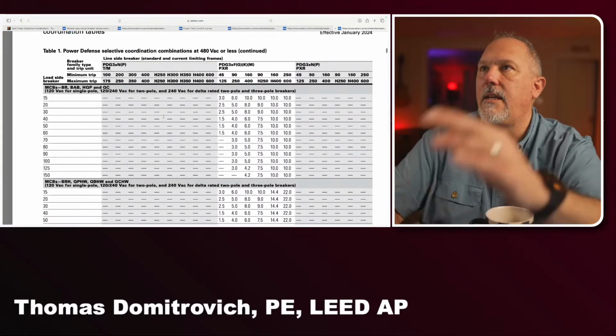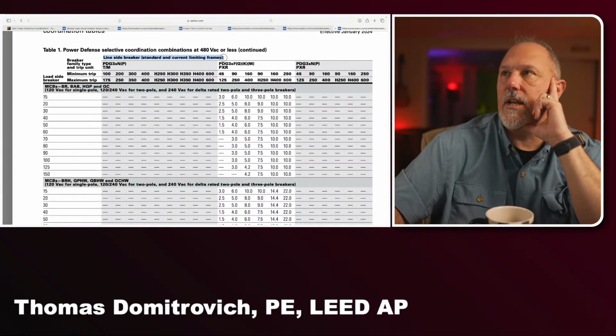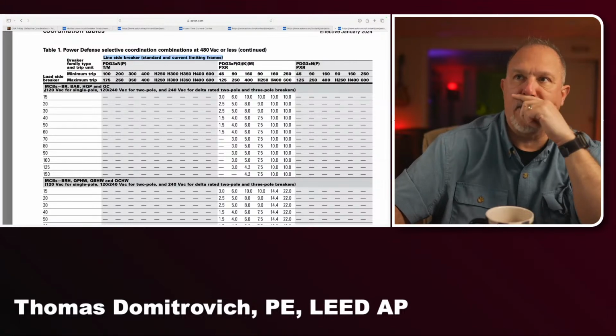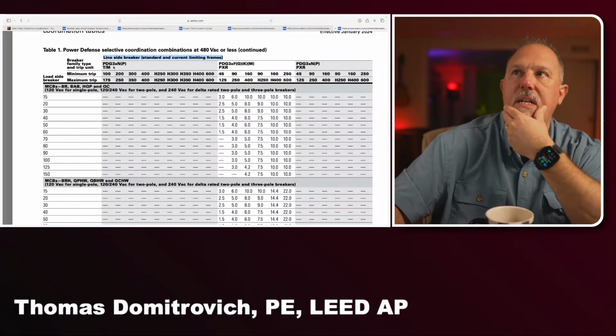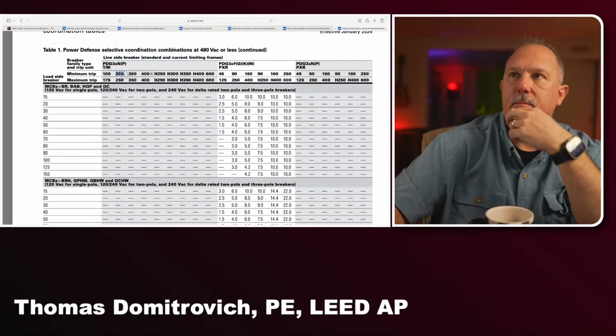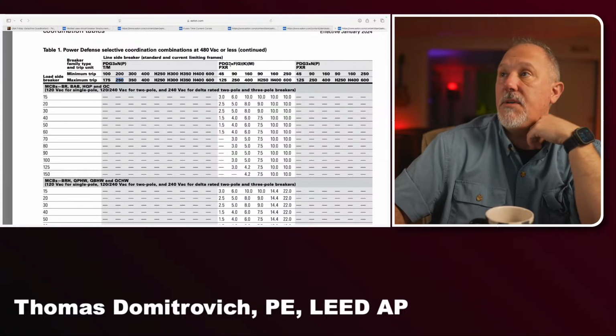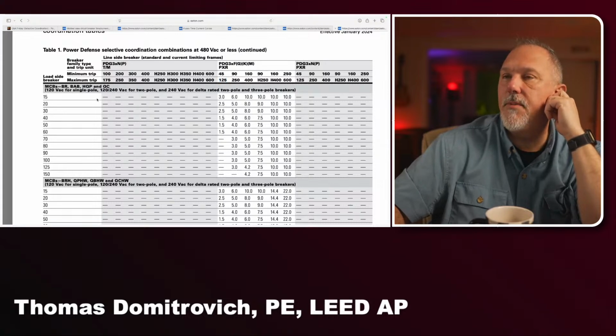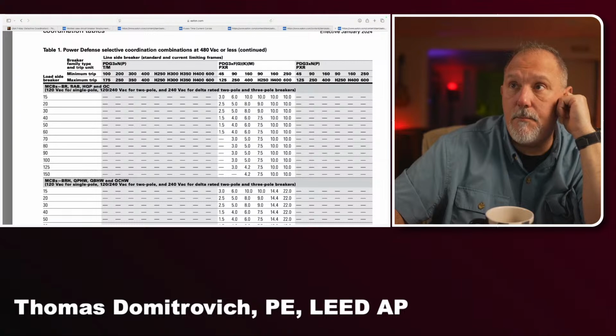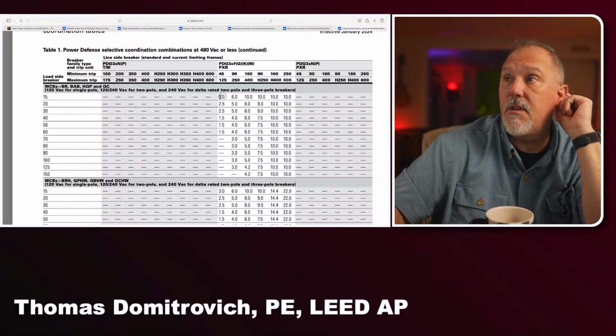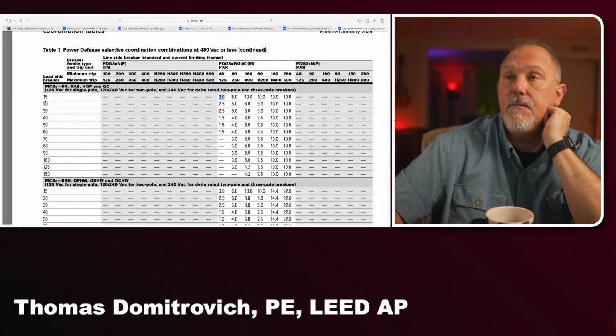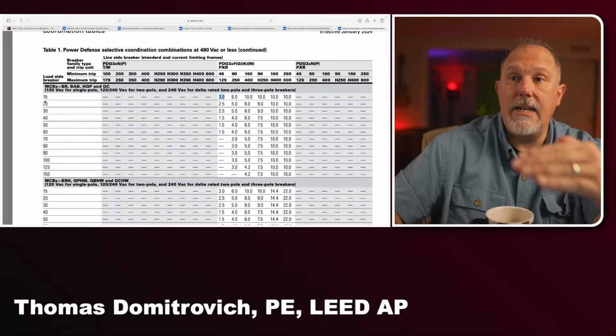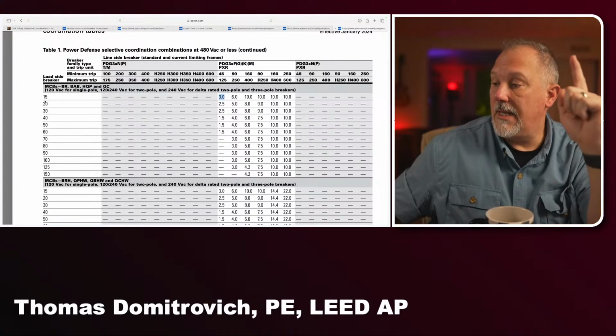Now, if you look at the Eaton breaker tables, line side breaker, standard current limiting. So this is the line side. This is the load side. This tells you that if you have a PDG3, 200 amp minimum trip, 250 amp maximum, you would need to go to a PDG3X for a 125 amp frame, 45 amp trip, for a 15 amp breaker downstream, BR, BAB, they coordinate up to 3,000 amps. Okay? What you're not getting in this table is this.